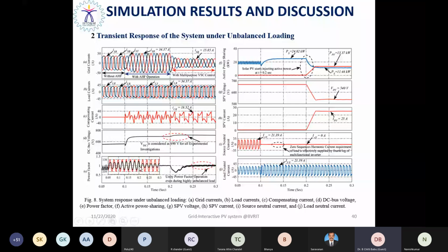And see the level of the power changes, and moreover, see the source neutral current without any controller. The neutral current can be carried by the neutral wire, but with the help of a three-phase four-legged inverter with a suitable control strategy, the zero sequence component becomes zero. So it is neutralizing the neutral current. So the third harmonic current is absent in the grid current, and see the load neutral current, the neutral current still flows in the load, but in the source it has been neutralized.